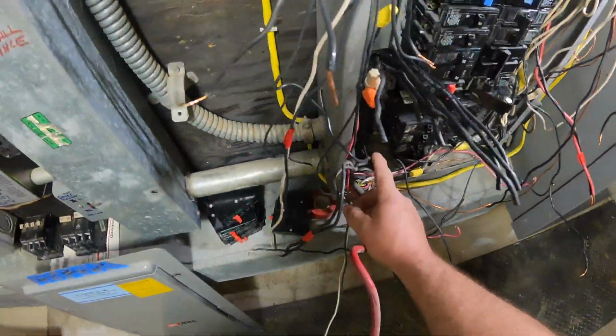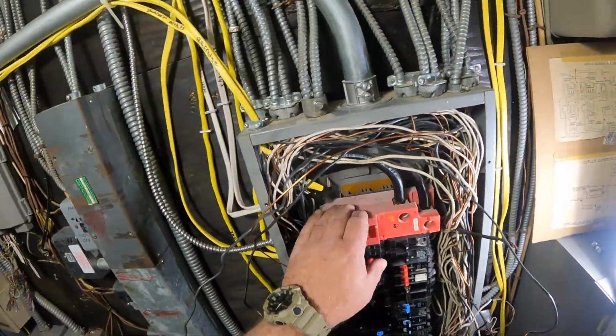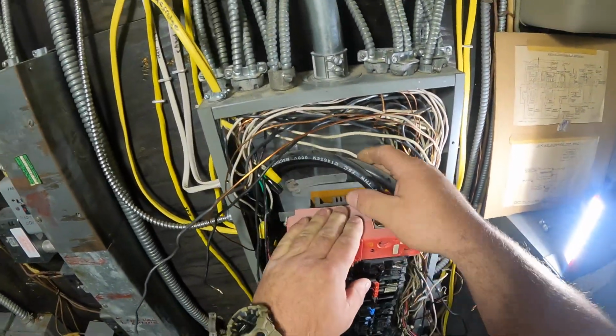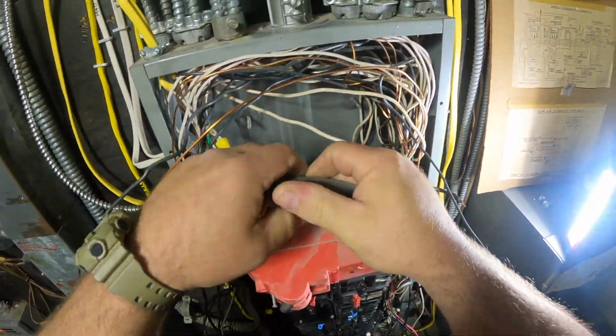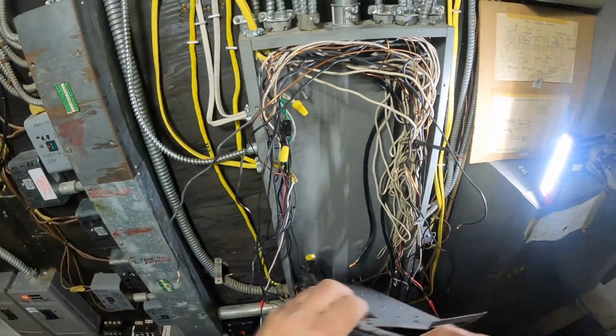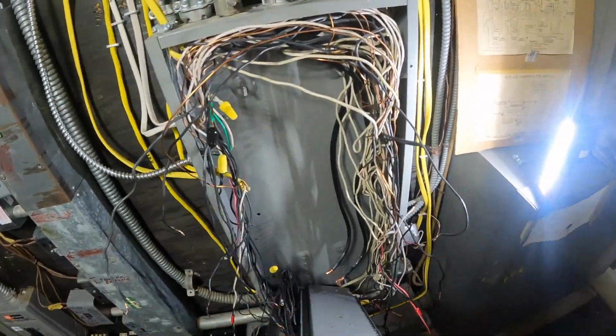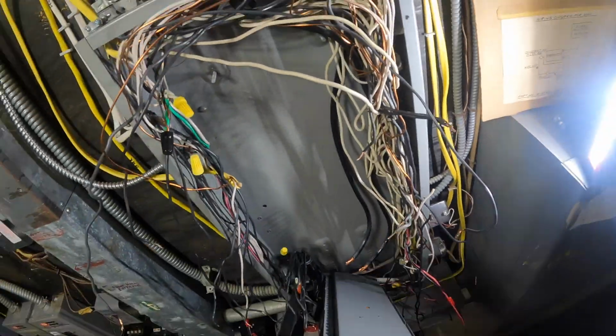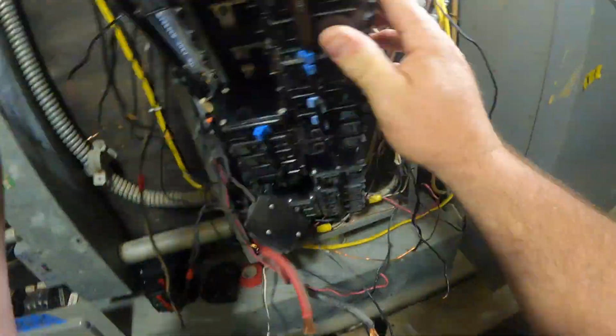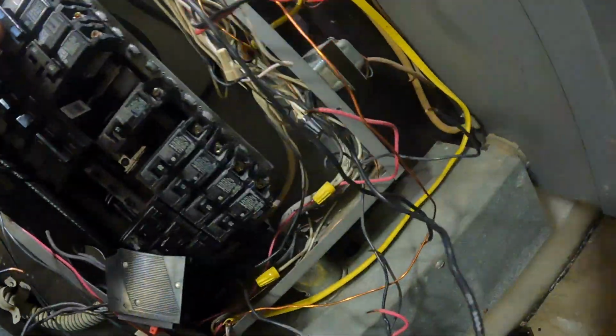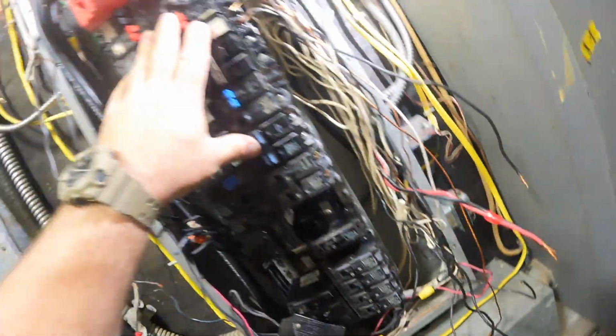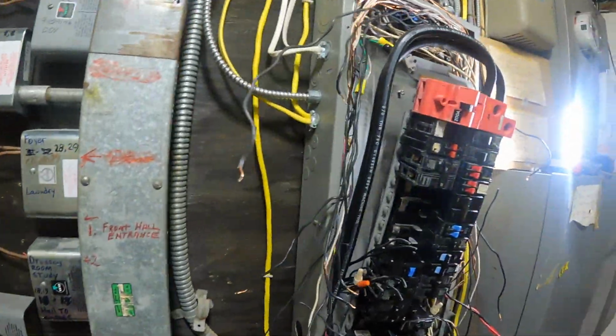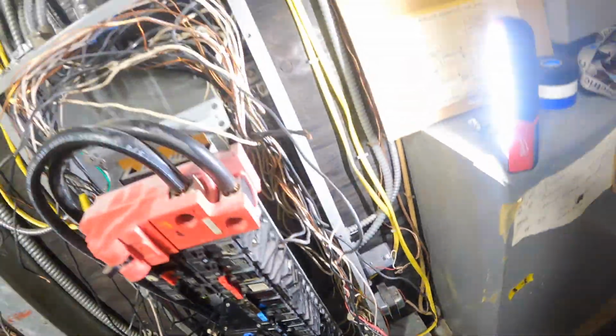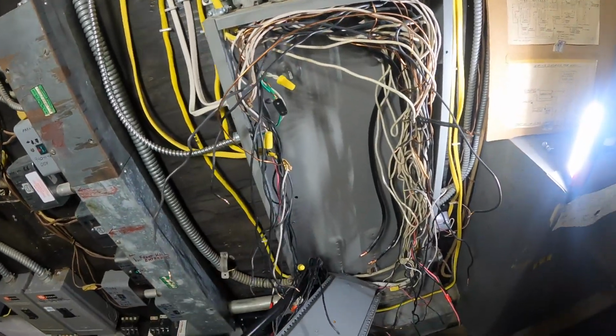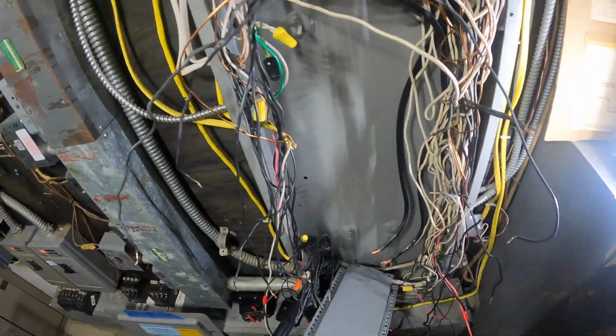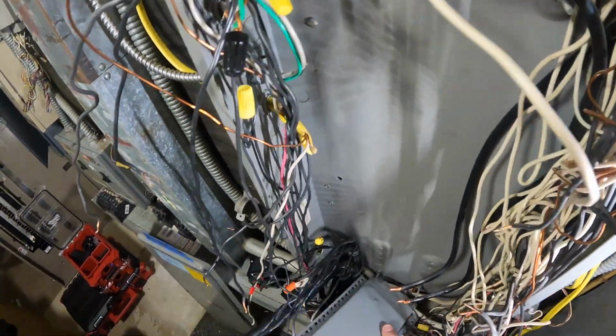The first order of business, as with any panel change, is to undo my ungrounded conductors, which I've done here. I've disconnected from the breakers. Now I'm able to loosen up the screws that hold this bus bar assembly and the main breaker assembly, and I'm able to disconnect it from the enclosure, which is going to give me more space to undo all my neutral conductors and all my grounding conductors. As you can see, I'm struggling here to get this out. I don't know if there's a screw. Oh, there's one more screw there at the bottom that I have to undo.